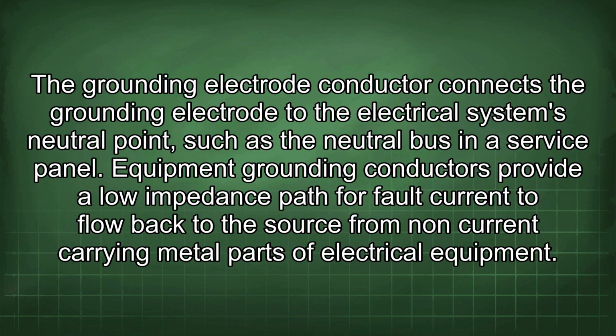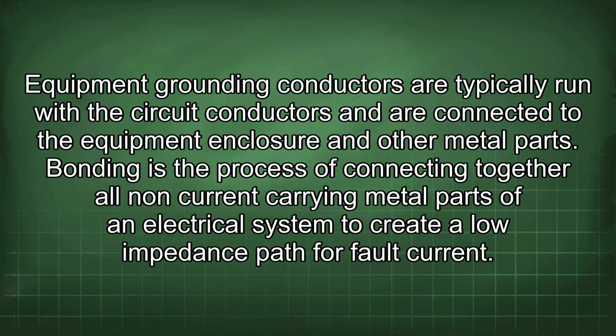The grounding electrode conductor connects the grounding electrode to the electrical system's neutral point, such as the neutral bus in a service panel. Equipment grounding conductors provide a lower impedance path for fault current to flow back to the source from non-current carrying metal parts of electrical equipment. Equipment grounding conductors are typically run with the circuit conductors and are connected to the equipment enclosure and other metal parts.